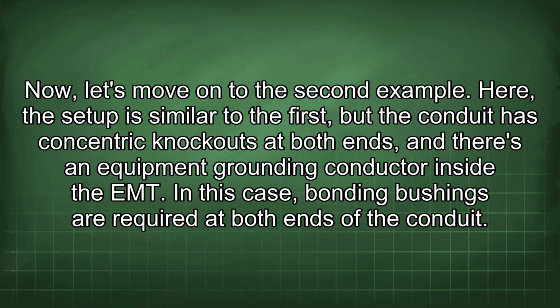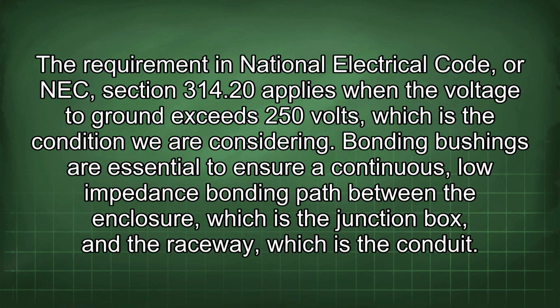Here, the setup is similar to the first, but the conduit has concentric knockouts at both ends, and there's an equipment grounding conductor inside the EMT. In this case, bonding bushings are required at both ends of the conduit. The requirement in National Electrical Code, or NEC, section 314.20 applies when the voltage to ground exceeds 250 volts, which is the condition we are considering.